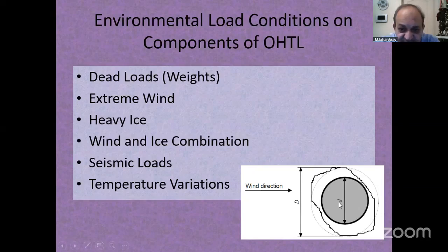I have shown in this picture here. This circle is the cross section of the conductor, and a uniform or non-uniform thickness of ice, or I mean wet snow or dry ice, can settle around the conductor, and when wind is blowing, the surface area affecting the conductor increases. So considering wind and ice combination is very important in loadings of structures. Seismic loads may also be considered in the design of transmission line structures, but as I told in the previous slide, they do not play an important role in loadings of structures.